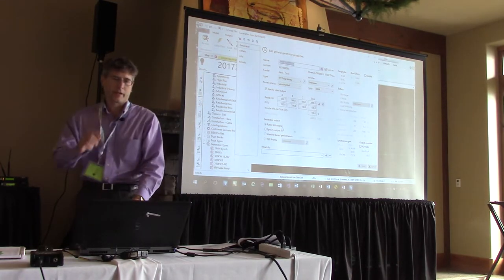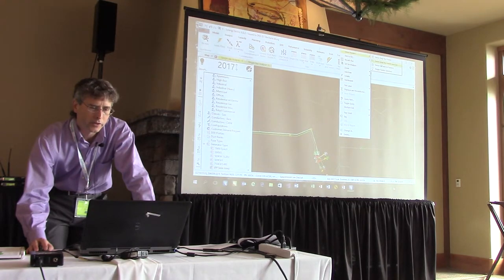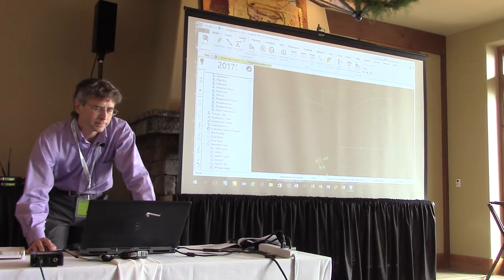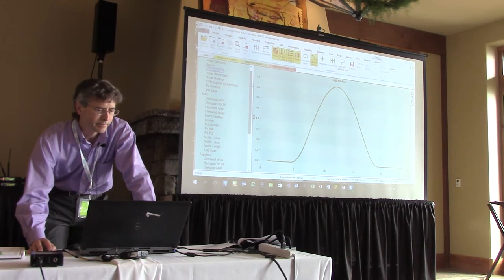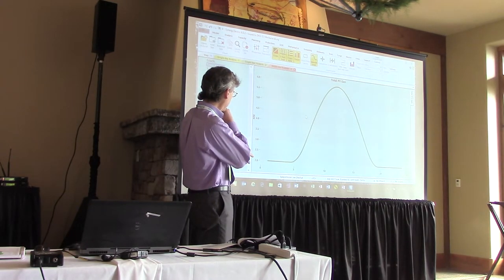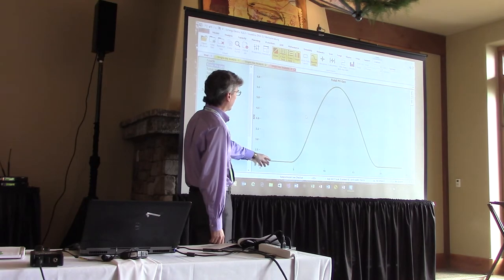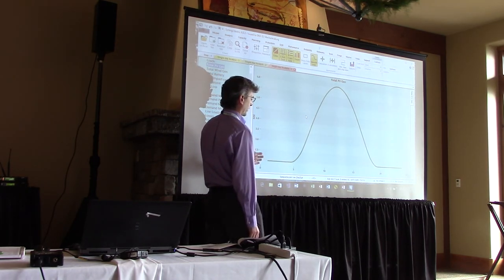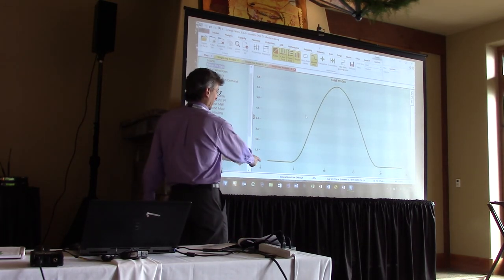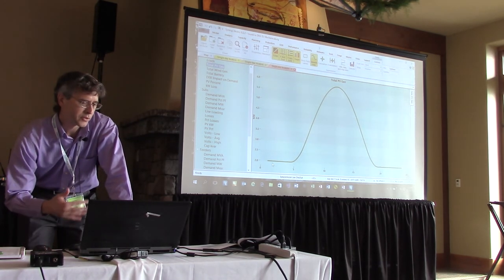But it's not going to work well over time. If I set rated KW output on this and run the single day analysis, look at the PV generation — see how this thing is starting at two megawatts at one o'clock in the morning? How could I have two megawatts of generation at one in the morning? That's because I just set rated output, so it doesn't care what time of day it is — you said you want rated output, it's going to give it to you no matter when. So this generator would basically be running in Alaska where it's daylight all the time. That's the drawback of setting these things up statically.